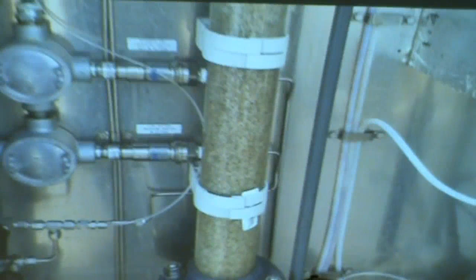In the event that we overpressure the sample system, it will push the wet leg out, up, around, back over here, and the wet leg will disappear. At this point our wet leg is situated right about there, see it? There's the wet leg right there. So we're full, but if we overpressure that, it would blow all of the pressure or wet leg out, and we'd be done with that.